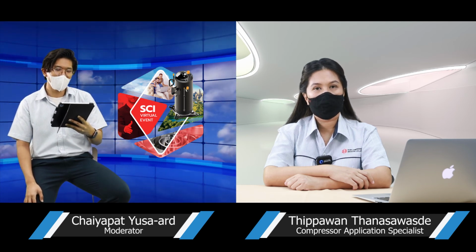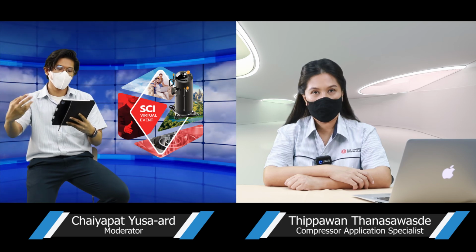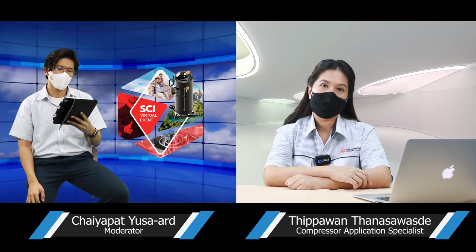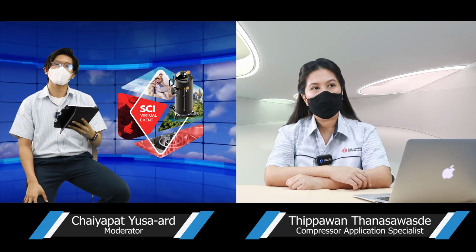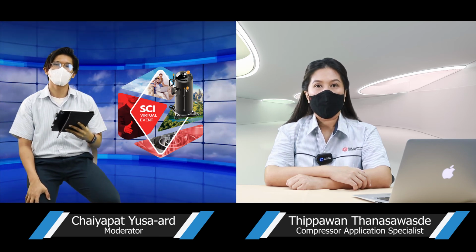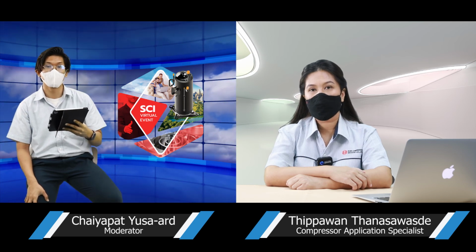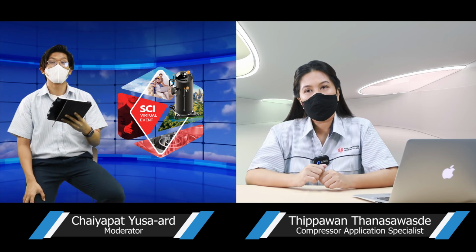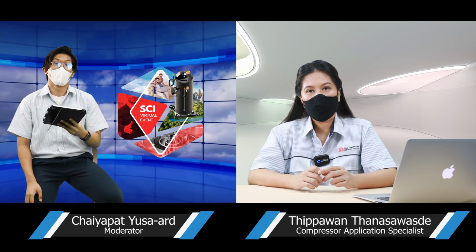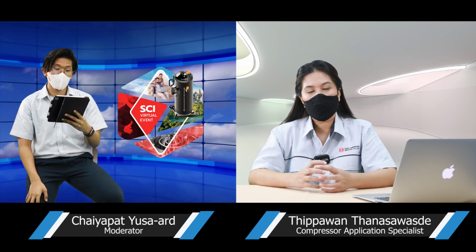All right. This question is very interesting. The 128cc itself is big, but in case we want to connect it in tandem, what is the maximum number we can go? We can connect our 128cc as many as we can, as long as we can manage the oil level in the running compressors at all times. Oh, right. So it's not really about the number. It really depends on the oil management, as long as you can keep that oil level above the minimum level.